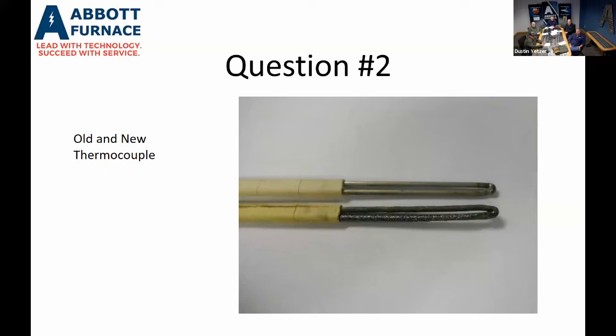Some of the expensive thermocouples like the R's and the S's can be sent back in to be recertified and get a recertification with them. But if you have type K's in your furnace, that's the picture here. They're pretty much a throwaway thermocouple once you use them. The picture shown here is what happens with a type K thermocouple after about 3 months of use in a furnace that's running at 2050. This is what they call the degradation of the thermocouple, or drift, if you will.